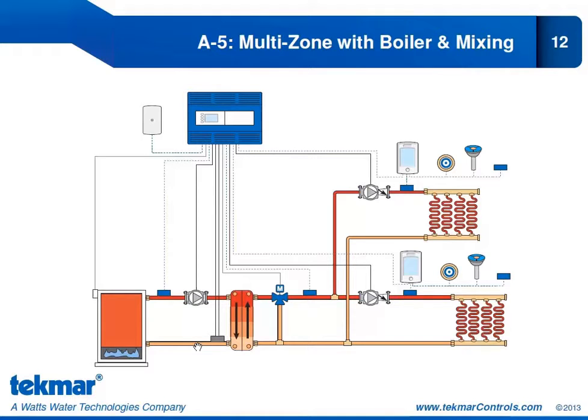So if these temperatures do approach freezing, then in this case we cannot stop the operation of this pump because we need this pump to be on for flow through the boiler. We will cut power to both of these zone pumps instead. And we'll look at the wiring of this freeze protection aquastat when we get to the technical training segment, which will be our very last training segment, number 8 in this tekmar Snowmelt Training webinar series.